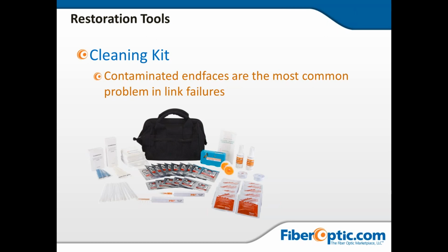Again, the Pro cleaning connector cleaners, the CS-125, is good for cleaning through the bulkhead and cleaning the far ferrule of the far connector with that wiping motion. Some of these other swabs come in really nicely because they're wide enough to put a lot of pressure on the inside of a mating sleeve. We've done enough testing to identify that the sleeve in many situations is cracked or has its own dust, debris, and contamination on it.